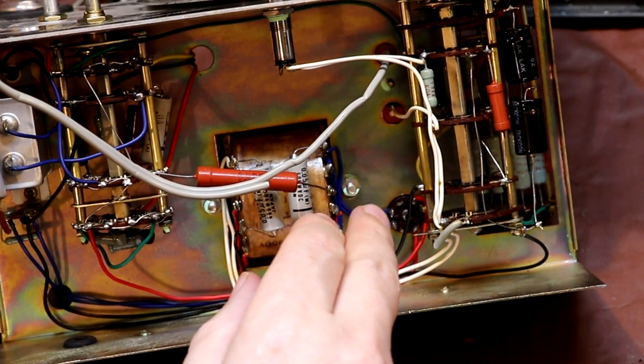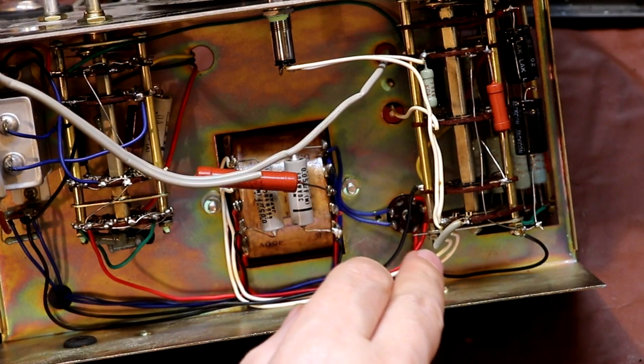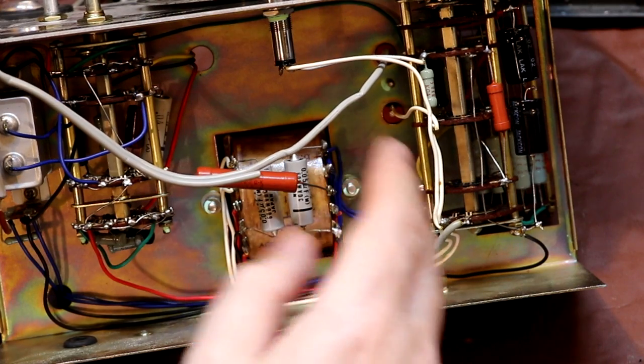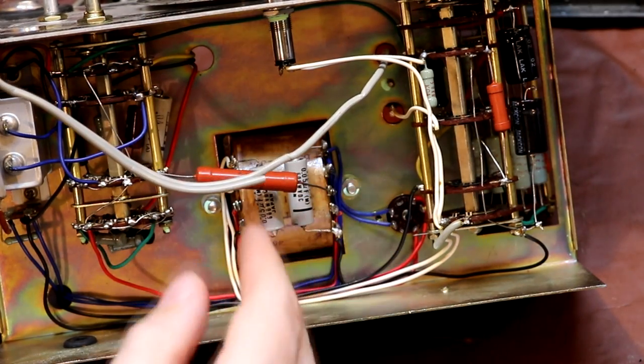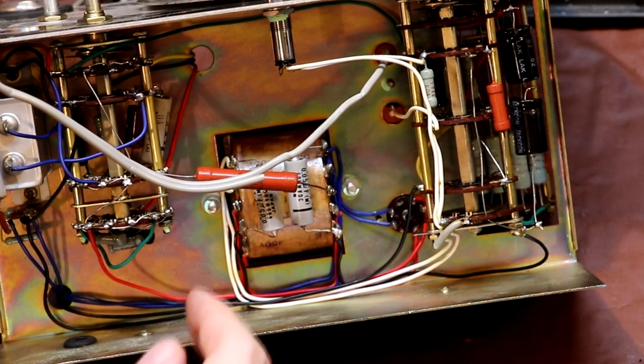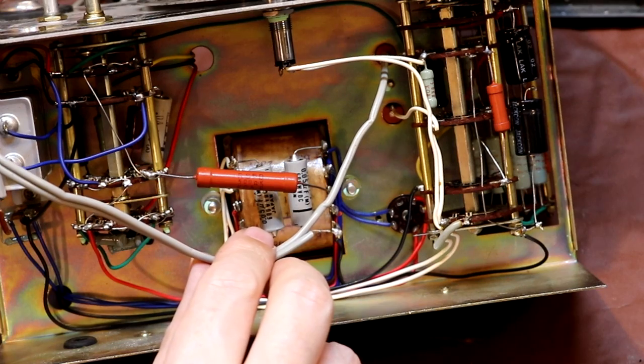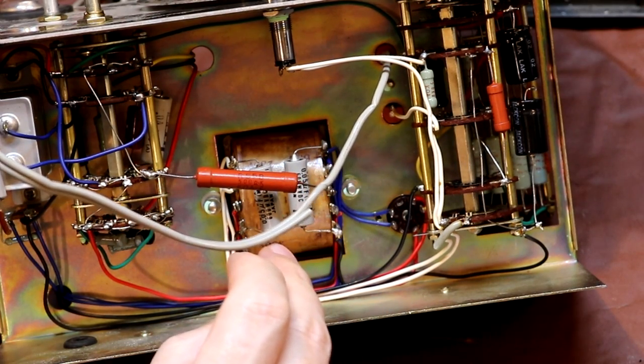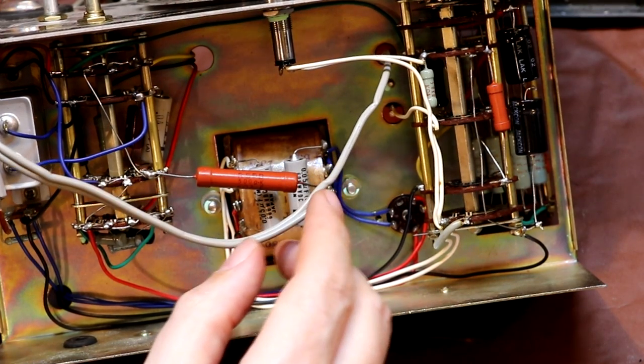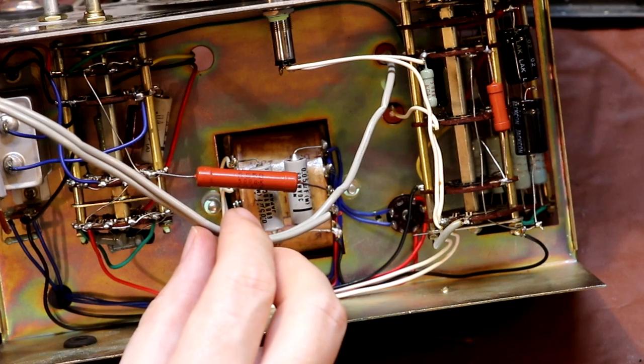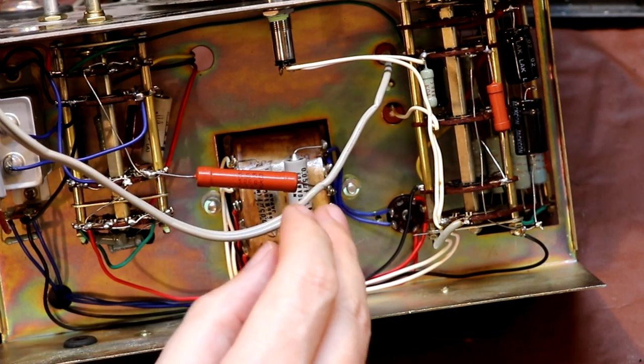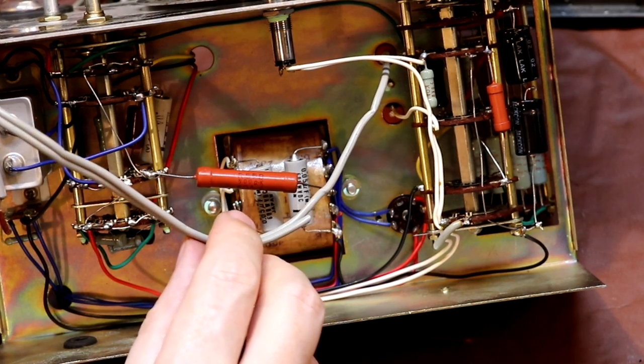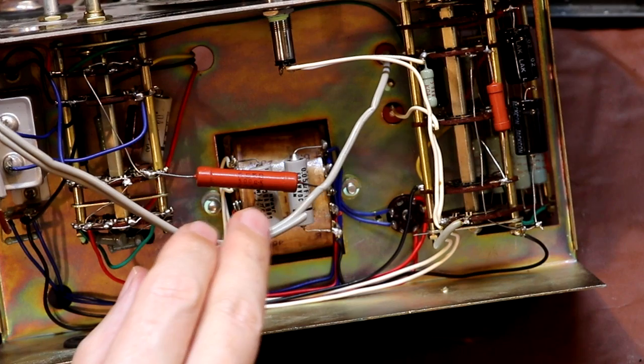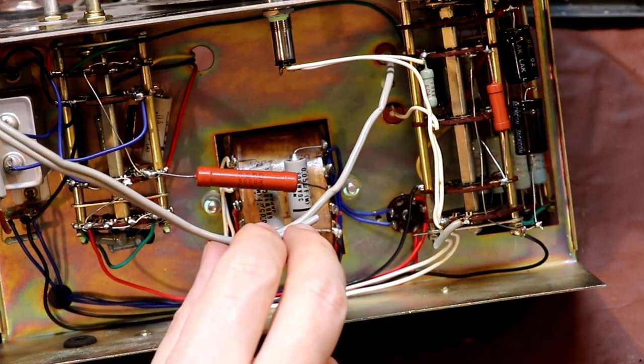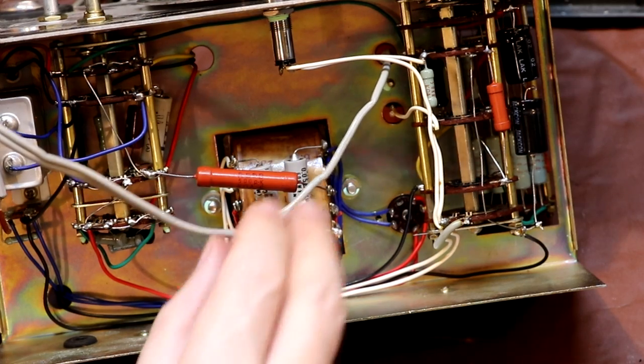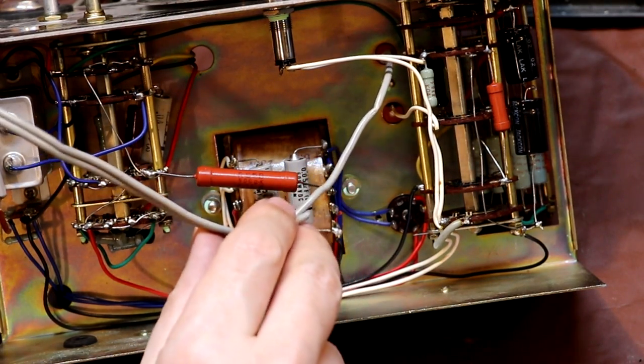Of course for my mains wiring, I prefer to have the live side connected to the switch so that we're actually switching the power on and off to the device, and I also prefer to have the fuse in the live side rather than the neutral side, because one of the problems with having the neutral supply connected to the fuse is, if you get a fault to ground, a live connection to ground, the live supply cable isn't fused if the fuse is in the neutral connection. So you can pass an awful lot of current to earth. And in fact, rather than the internal fuse blowing, what would happen is we'd be relying on the 3 amp fuse in the plug. Now that's okay to some extent, but what's the point in putting a fuse in here if they don't bother to fuse the live supply?